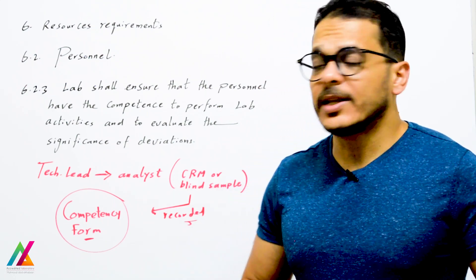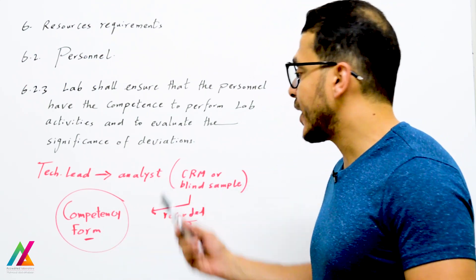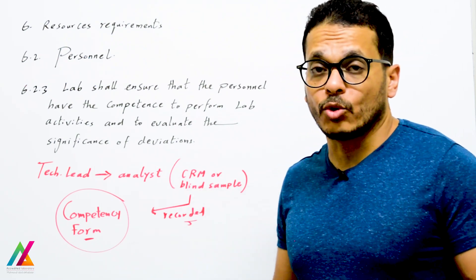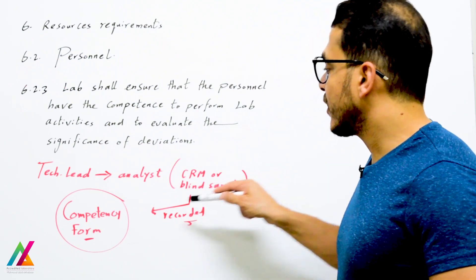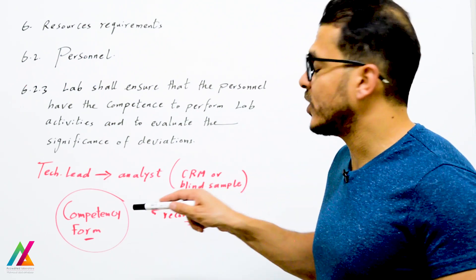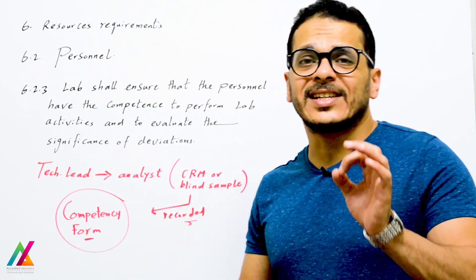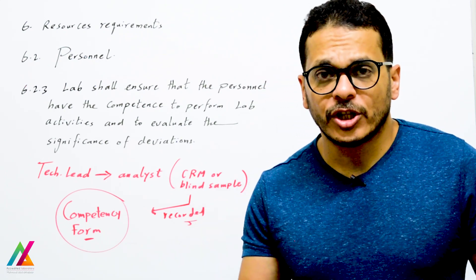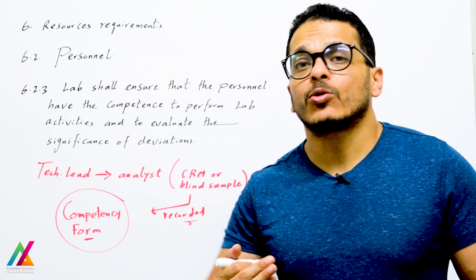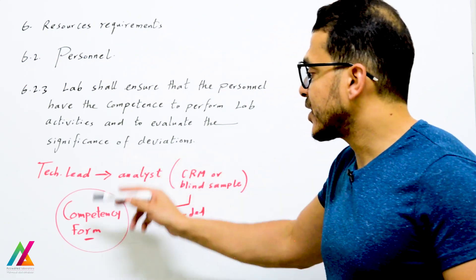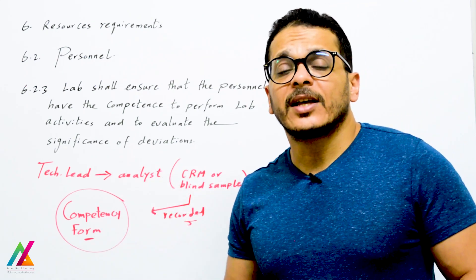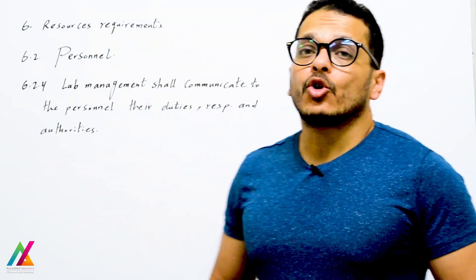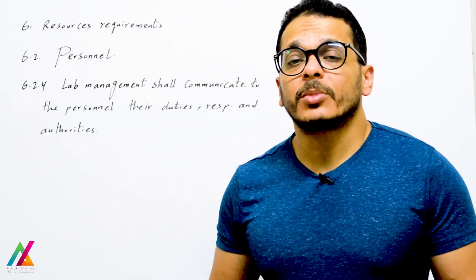Lab management shall not assign duties or responsibilities to personnel before ensuring their competency. To ensure competency technically, each unit will provide the new analyst with a certified reference material (CRM) of known concentration for each parameter, or a blind sample. Results of this test are recorded in a competency test form, and if results are within the acceptable range, the technical lead can authorize the person to perform the lab activity. This competency test shall be repeated every year.